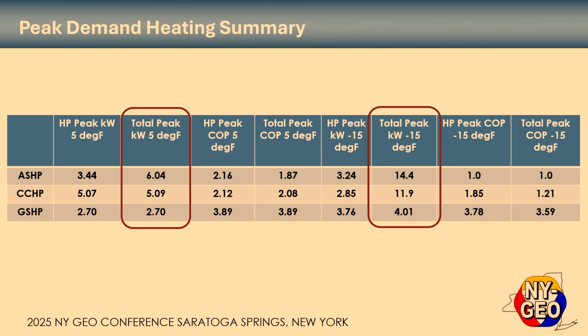And the other thing, so the 5 degrees versus the minus 15, 5 degrees is closer to what you're supposed to design to according to Manual J, right? It's the 1% condition. And the Clean Heat Program in New York State says that a fully sized system is sized to meet the load at the 1% design condition. But I do agree that the minus 15 happens.